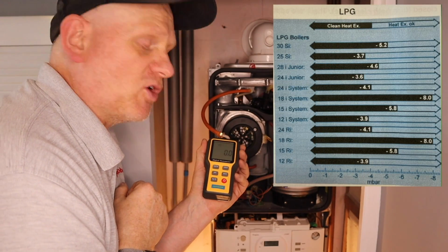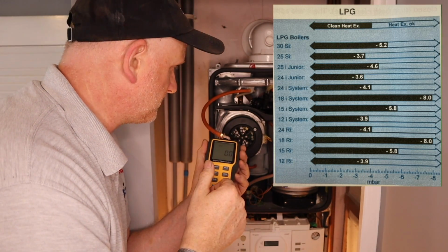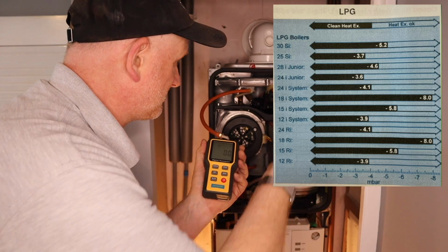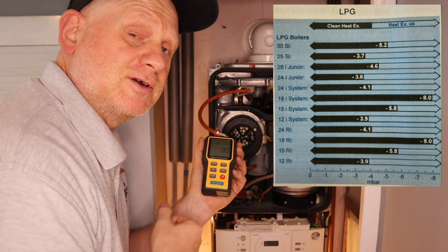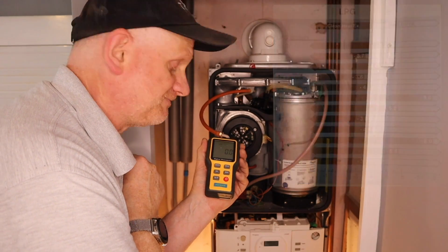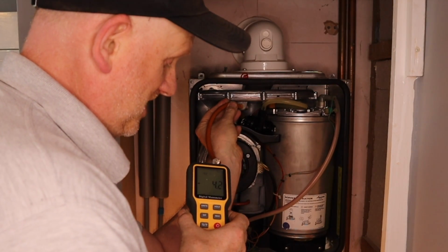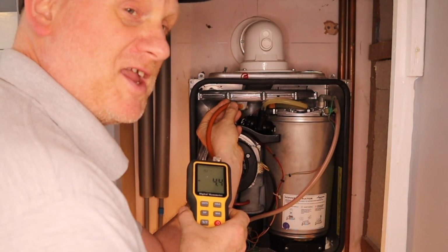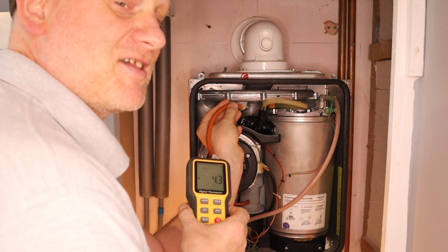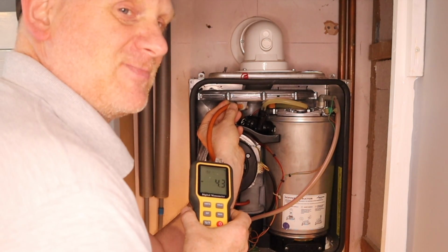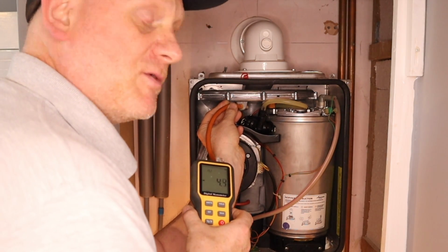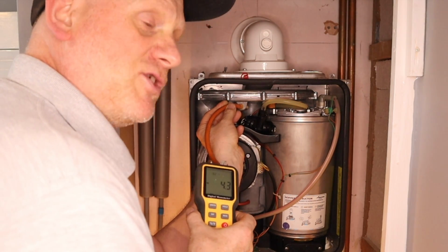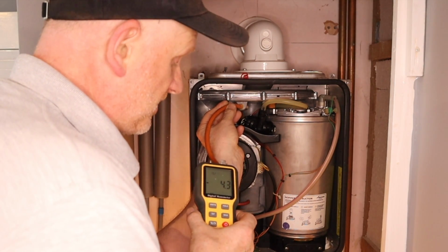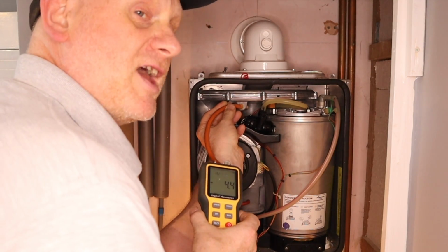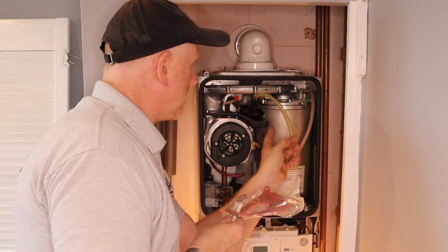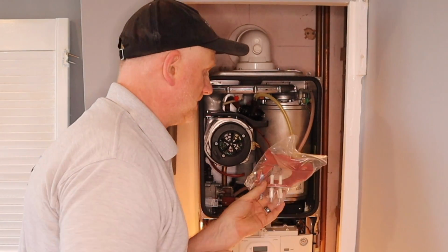But if it's less than minus 4.6, then I will need to strip it. But I am going to strip it anyway, because I need to look inside. So let's get a tap on and see what it reads. So you can see it's reading 4.3, 4.4. So that's saying it's just outside the readings. I'm going to strip it and clean it, and then we'll see what readings we get after it. So this is how you can tell whether the heat exchanger needs to be stripped or not, by just doing this little test.